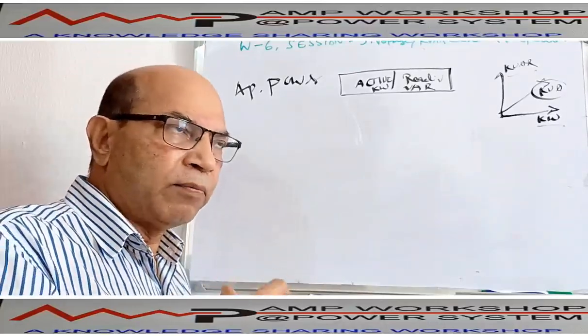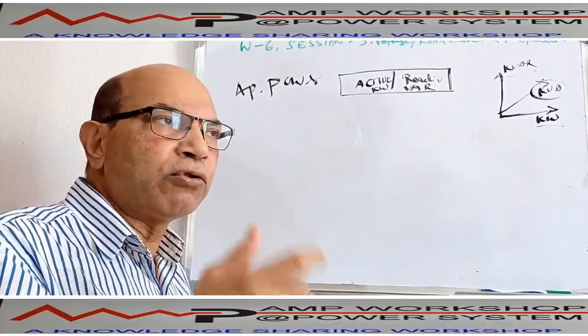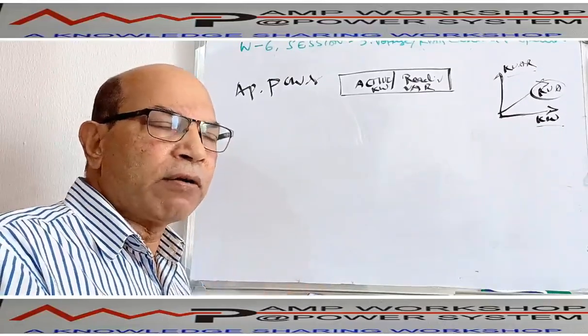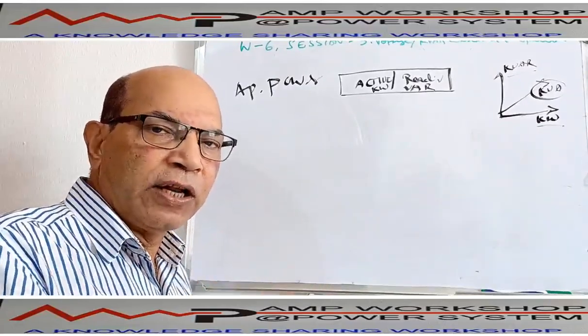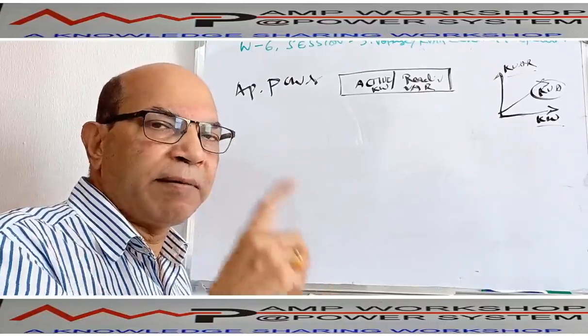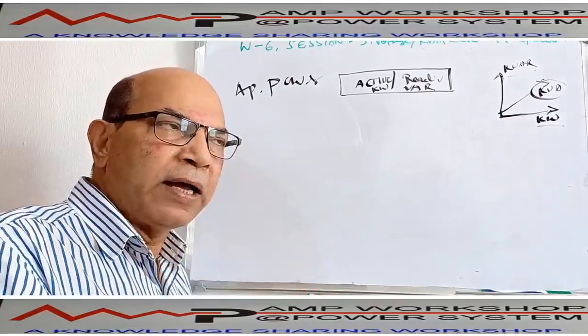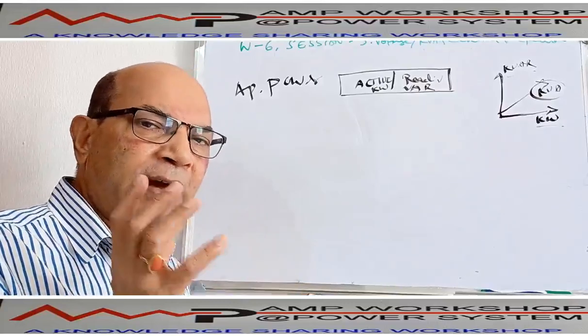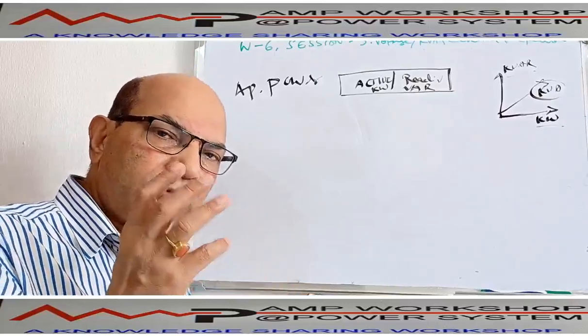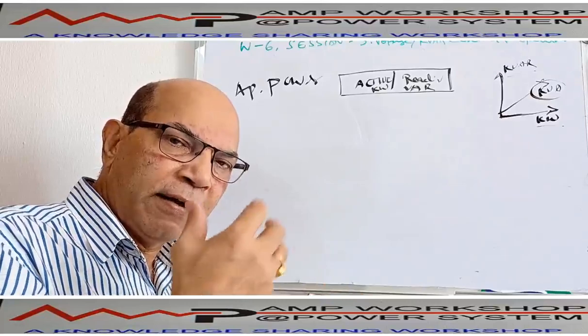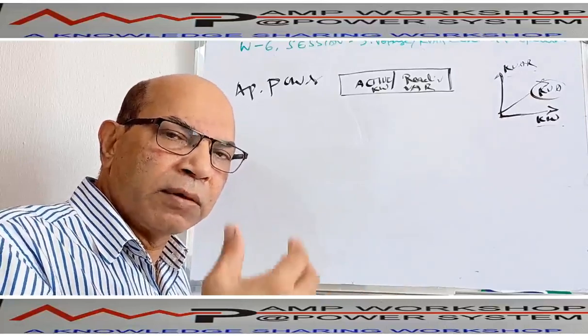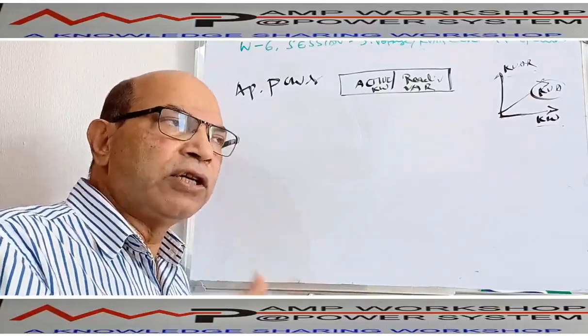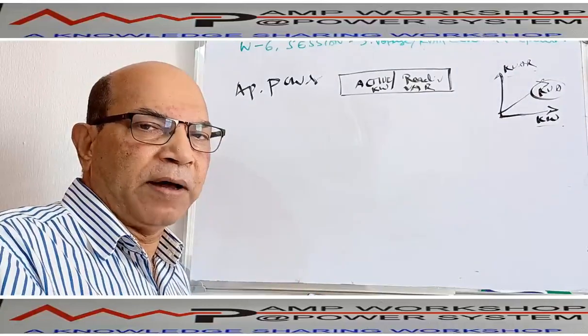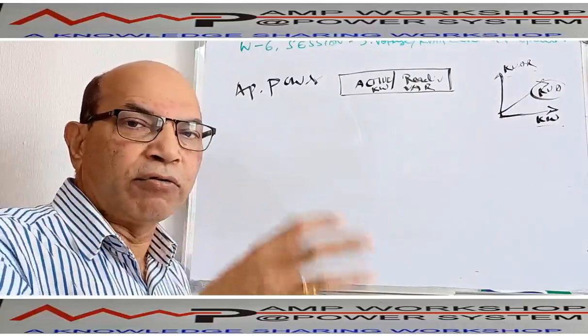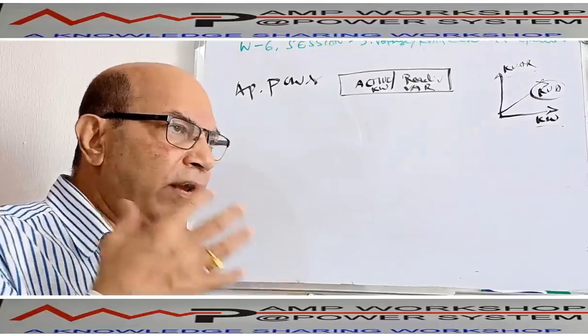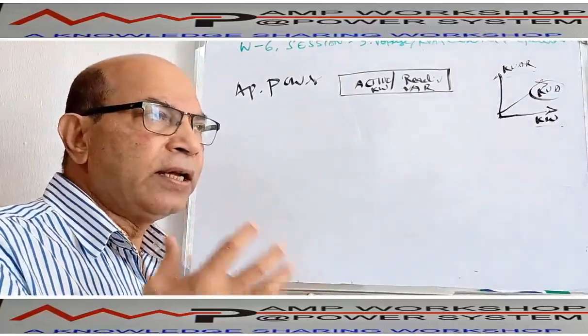But most of us have a motor winding, when the motor is rotating and running a pump or a compressor or any other rotating equipment. Suppose the motor is rotating a fan, you can say the fan is rotating, that is the mechanical part, the active power. But the motor winding is also getting magnetized by current, so it is also drawing magnetizing reactive current. But that part we cannot visualize, only the rotating part we can visualize. So when any power is flowing through a line, it actually has 2 parts.